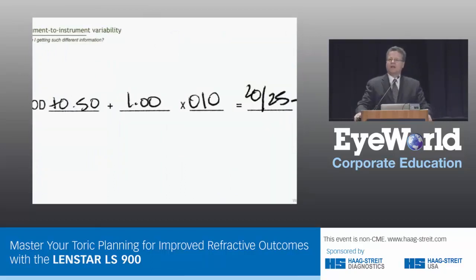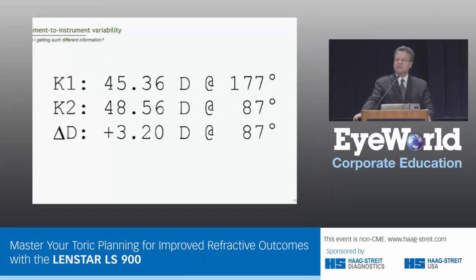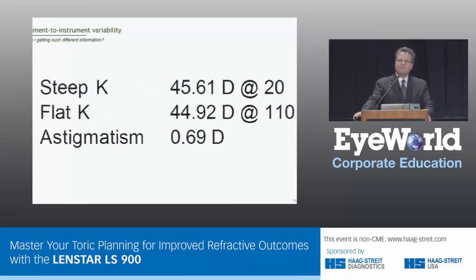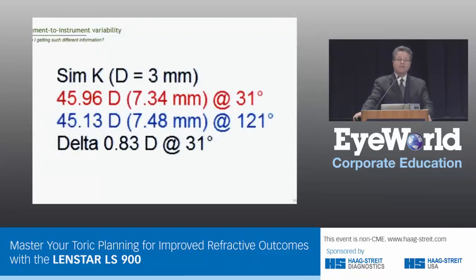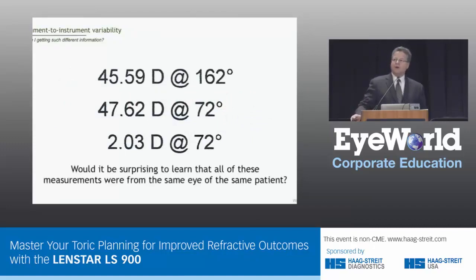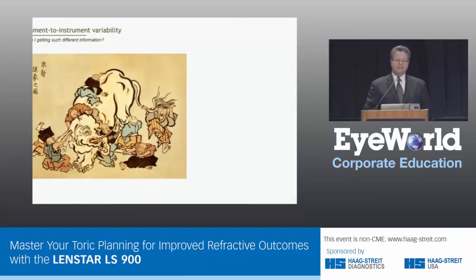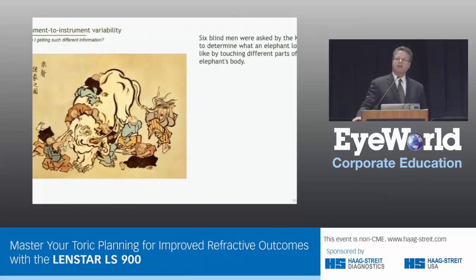So what is it that we need for the Toric IOL? There are lots of ways to get information. We can look at the patient's spectacle refraction — here we have about a diopter of against-the-rule astigmatism. We can look at small zone autokeratometry — here's a little more than three diopters with the rule. Some simulated keratometry, a little more than half a diopter, looks like against the rule. Ray tracing keratometry, a little more than three-quarters of a diopter on the oblique meridian. And more small zone autokeratometry, about two diopters with the rule. Would it be surprising to learn that all of these measurements were from the same eye of the same patient? And this is one of the problems we have with the Toric IOL.